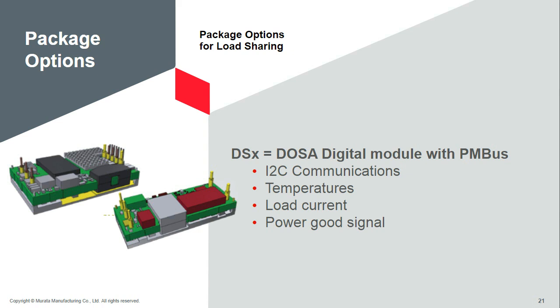Now the DSE or DSQ is also available with a PMBus, which we didn't discuss in this presentation. This might be my next presentation. There's a lot that goes into the PMBus. So this is an I2C communications line, okay, that's commonly used in all kinds of electronics, especially in the communications field. You can get some telemetry information from the power supplies, such as temperatures, load currents, and there's even a power good signal on the output of the PMBus.